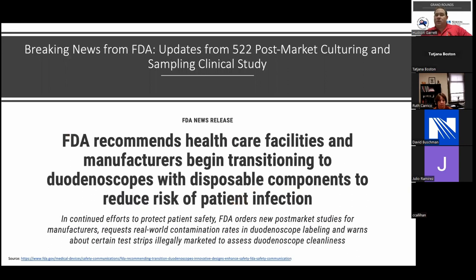And so the first one that came out was really saying, can we get away from just completely reusable devices and get to something that might have a disposable component, preferably one that's sterile? In this particular example, sort of similar to what we talked about with the glucometers, here it was the distal end cap in the elevator. So they went to the manufacturers and said, we need you to innovate. We need you to do something that's going to eliminate that risk so we can actually solve this problem.